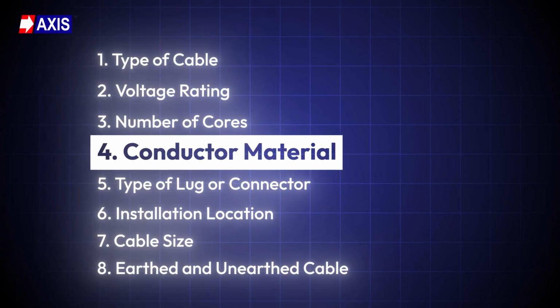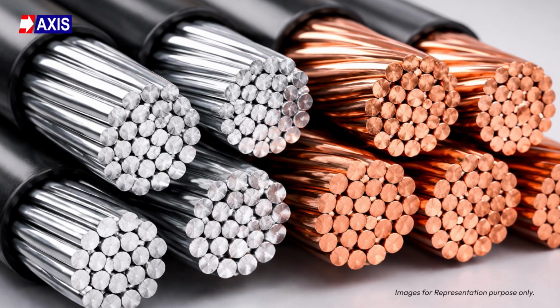Number 4, the conductor material. The cable conductor can be aluminum or copper, but the lugs and connectors must be compatible with the conductor material to ensure proper electrical contact and avoid overheating.